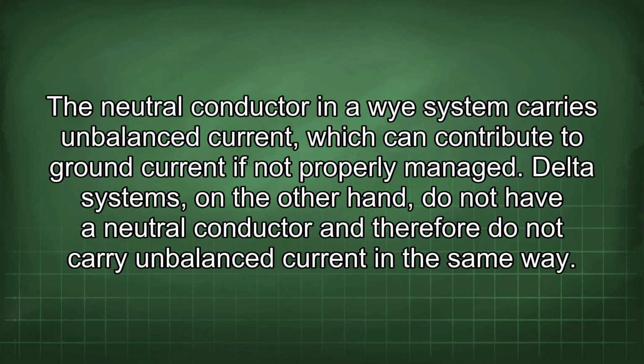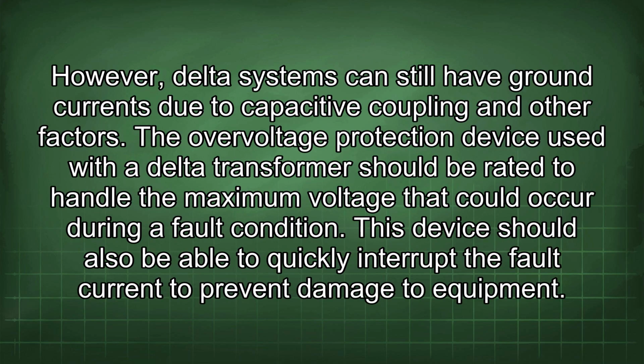The neutral conductor in a Y system carries unbalanced current, which can contribute to ground current if not properly managed. Delta systems, on the other hand, do not have a neutral conductor and therefore do not carry unbalanced current in the same way. However, delta systems can still have ground currents due to capacitive coupling and other factors.